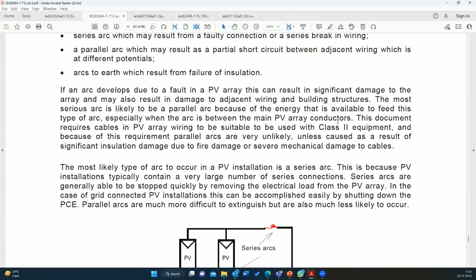So as I said, against parallel arc, of course, double insulation is the most important safety measure, but most of the time inside the combiner boxes the double insulation requirements are compromised. This is one of the reasons. If you look on Google, you can find several videos where combiner boxes are burning. It never stops and keeps on burning because the PV module is pumping energy into the combiner box. Double insulation is compromised. As a result, it catches fire.